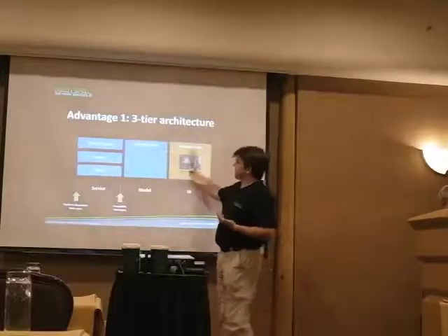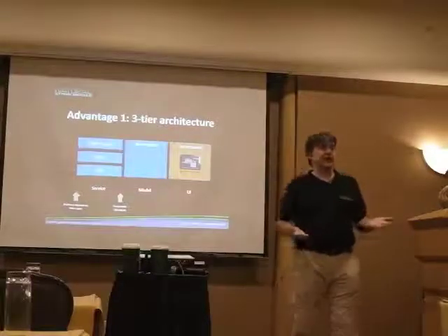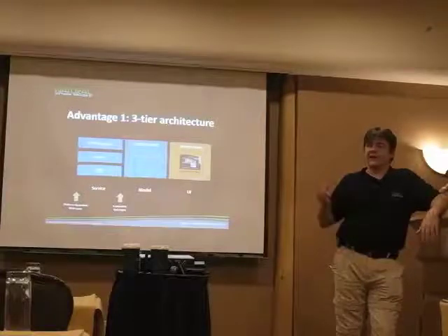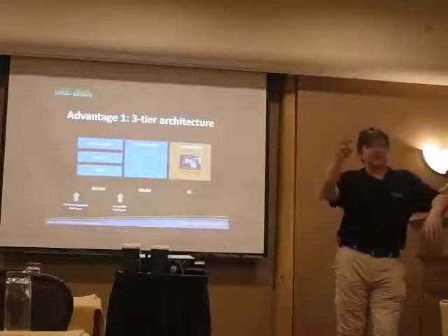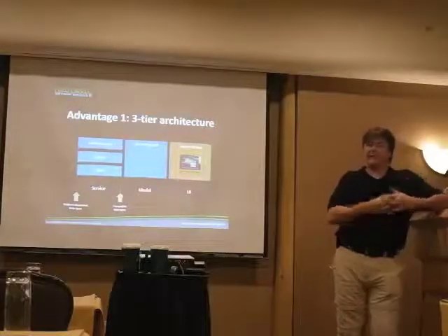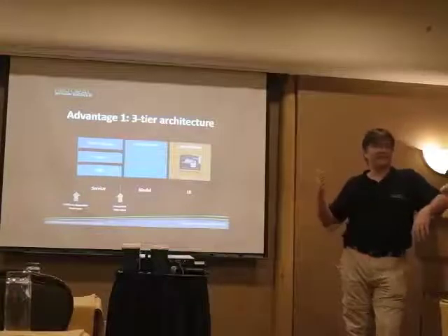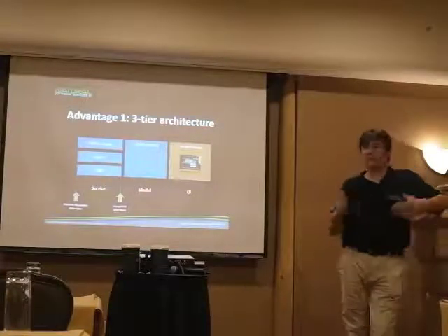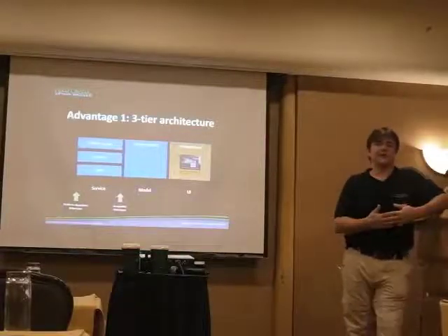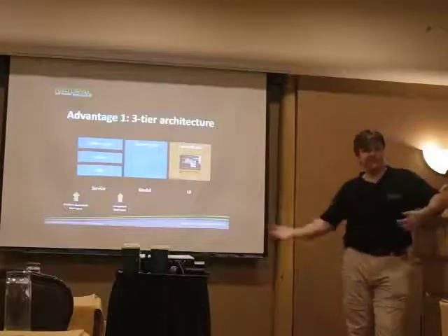And then of course the presentation layer only accesses the object model. And in the presentation layer, I'm saying, okay, I got a switched light or a dimmable light, and I want to have it on the web page at this location. And if I click on it, I'm going to have this pop up. But at that point, it doesn't interest me if it's working with KNX, AMX, if it's connected to the serial port or whatever. Presentation layer only concentrates on displaying objects of the same type in the same manner.